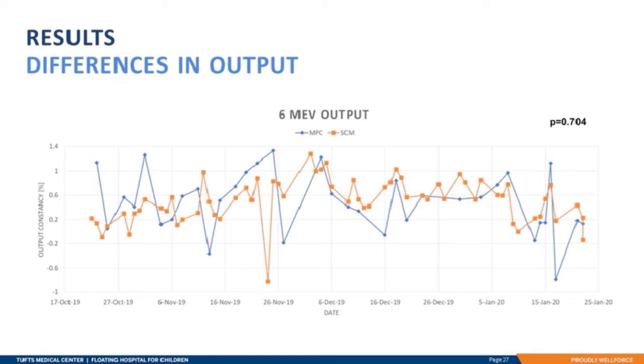For electrons, Machine Performance Check does not use a cone and looks at intensity of pixels from the EPID, while SunCHECK Machine does use a cone, and the daily QA3 uses ion chambers for output constancy. Therefore, output constancy for electrons for these two platforms are fundamentally different on multiple levels. Even with that, the two platforms for 6MeV tracked well together and also did not show a significant difference. Since the 6MeV beam was run every other day for Machine Performance Check, some large variations you can see recorded for SunCHECK Machine were days that this energy was not run for Machine Performance Check, and therefore we did not see the variation on that platform.